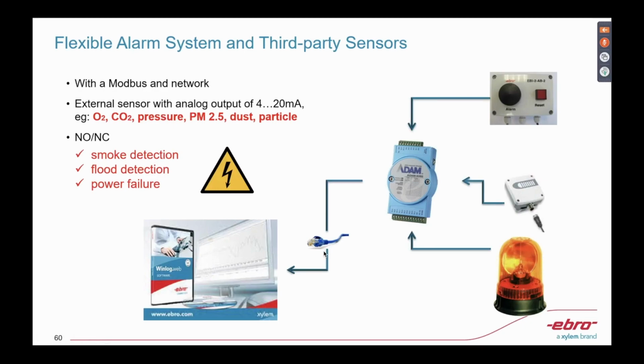This is the feature I really want to focus on, because our WinLog Web is very powerful. It is possible to combine it with third-party sensors as long as they have a 4 to 20 milliampere output. For example, you might want to measure O2, CO2, pressure, or dust and particles in your facility. We can integrate these third-party sensors into our system, so you only need one system and one alarm setup, which can also be combined with different alarm methods like a flashlight, a calling machine, or SMS, whichever you wish.